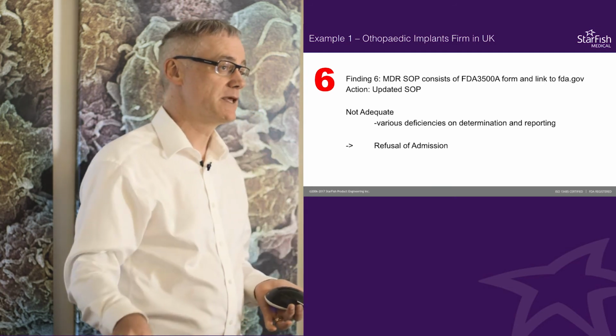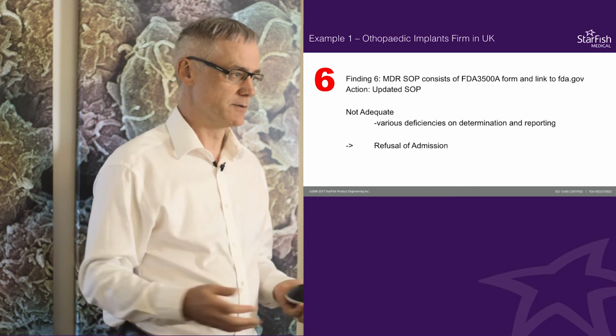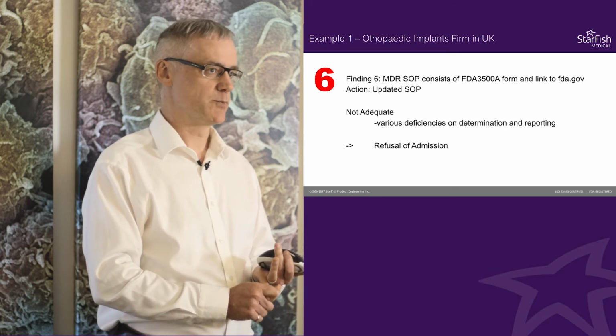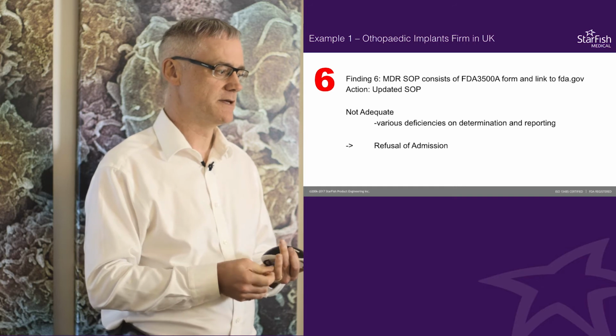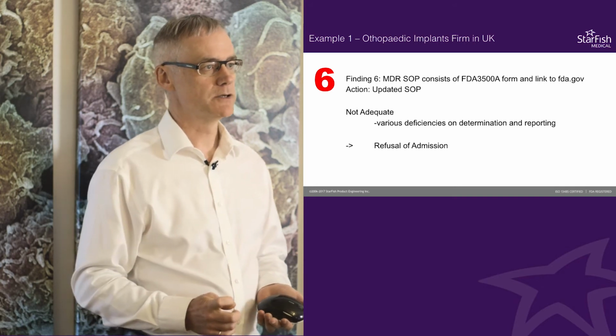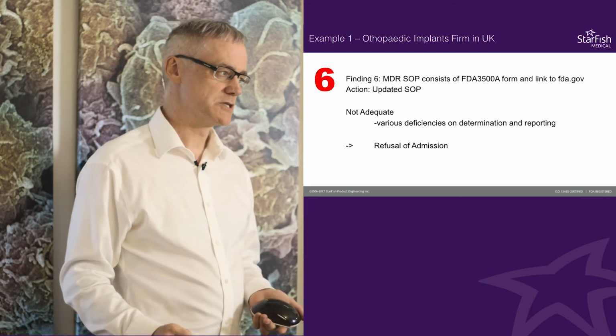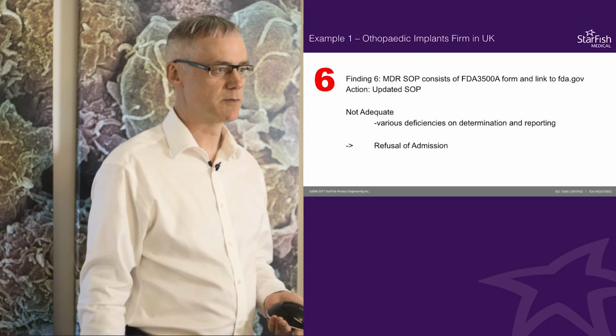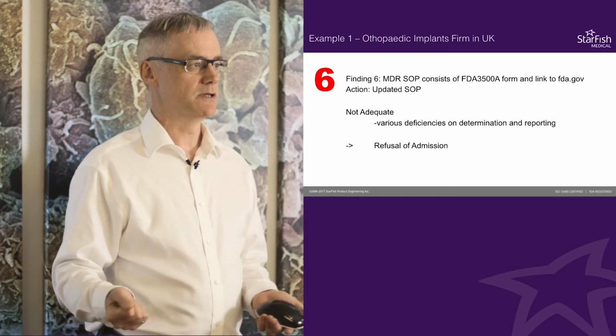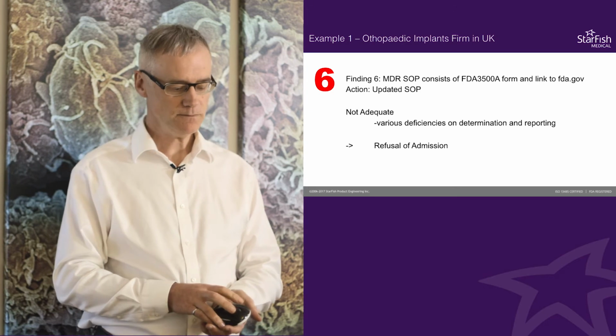Anyway, the company updated their SOP, and they basically didn't follow the requirements. So the finding was deficiencies both in the determination of whether something was reportable and in the reporting frequency. The outcome for this company was a warning letter and also refusal of admission, which is pretty common for imported products, meaning the FDA says you're not allowed to bring this into the US again until you can address these findings. So a pretty serious outcome for a company like that.